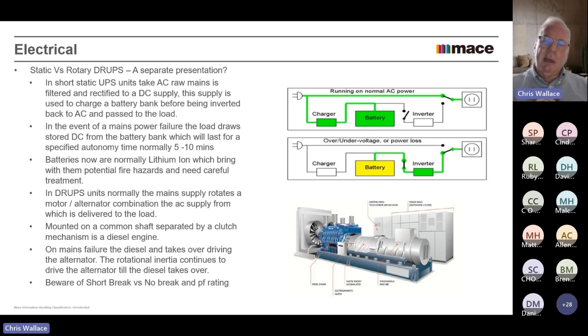The other thing is the rating that they normally sell these at in the catalog. They'll normally sell you these at a 0.8 power factor rating, which is just historical. That's what they used to use. 0.8 was everyone's favorite power factor. If you're using them to supply a data center load, which has a unity power factor or a 0.95 power factor, then you need to consider that, because the catalog rating is nearly always at 0.8 power factor. And I know situations where a combination of these factors have meant that people have ended up in court, shall we say.